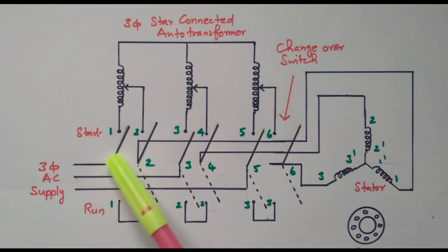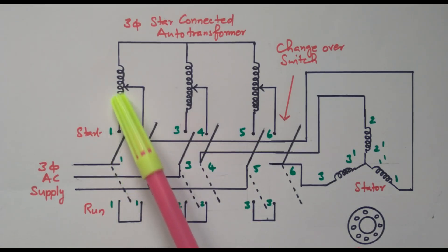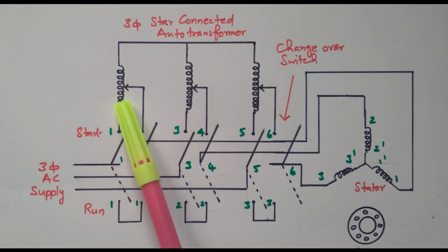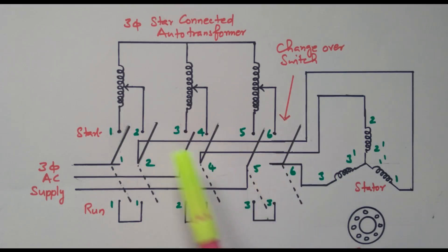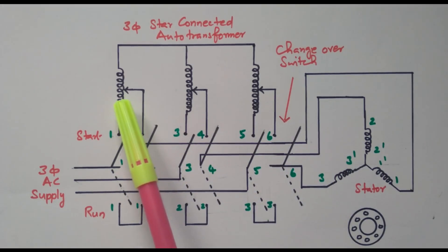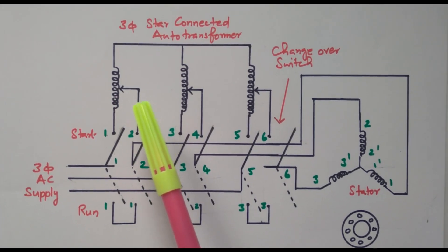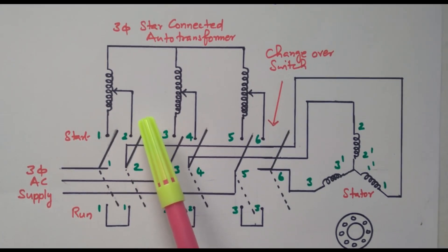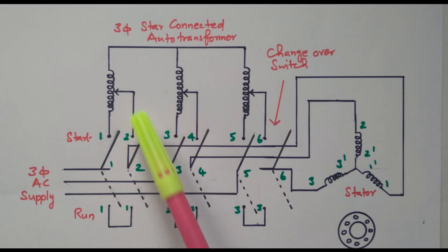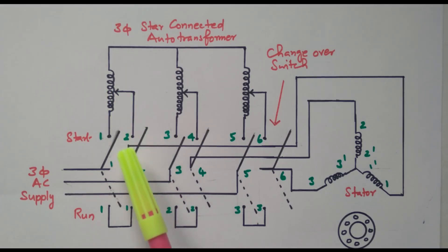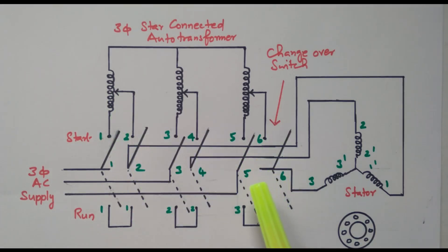Initially, the changeover switch is placed in the starting position — that is, through the auto-transformer. So initially, only a reduced voltage is applied to the three-phase induction motor using the auto-transformer. Only a smaller amount of voltage will be applied to the stator. After some time, when the speed of the induction motor gradually increases, the voltage is gradually increased by using the auto-transformer, so the voltage applied to the stator gradually increases.